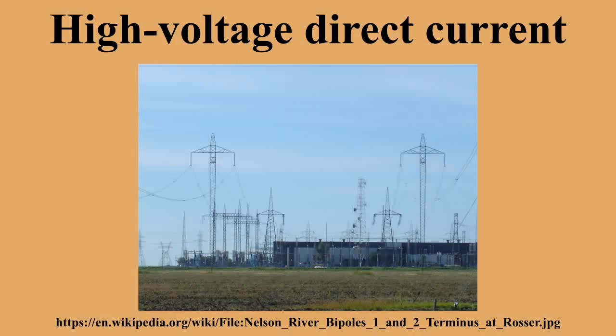HVDC allows power transmission between unsynchronized AC transmission systems. Since the power flow through an HVDC link can be controlled independently of the phase angle between source and load, it can stabilize a network against disturbances due to rapid changes in power. HVDC also allows transfer of power between grid systems running at different frequencies, such as 50 Hz and 60 Hz. This improves the stability and economy of each grid by allowing exchange of power between incompatible networks.